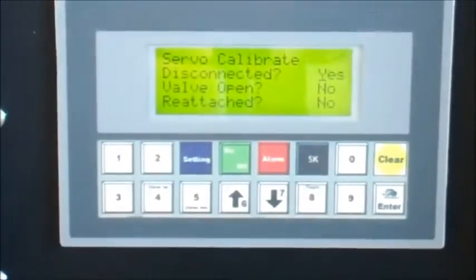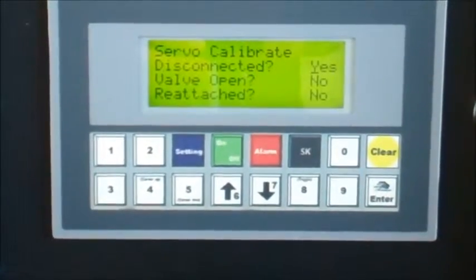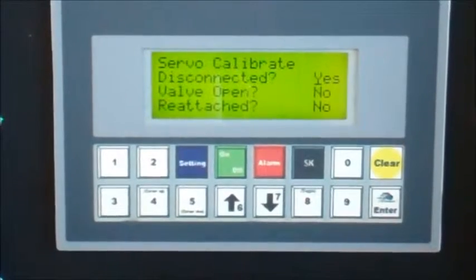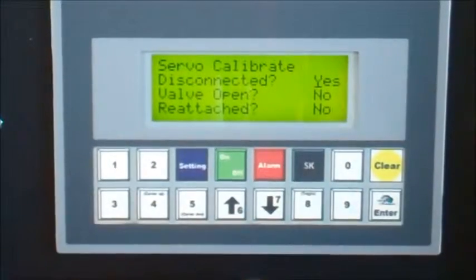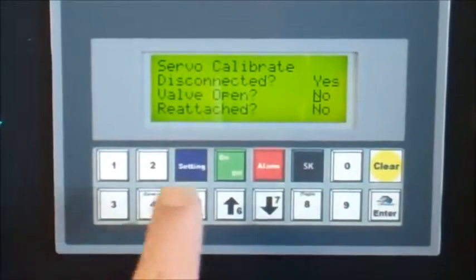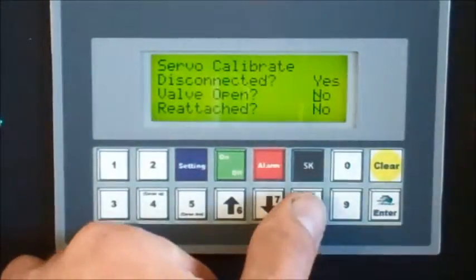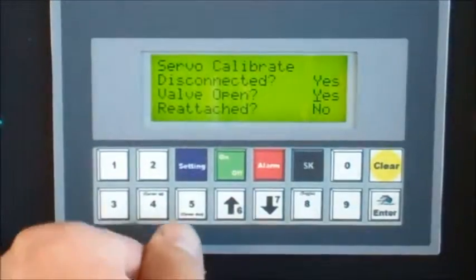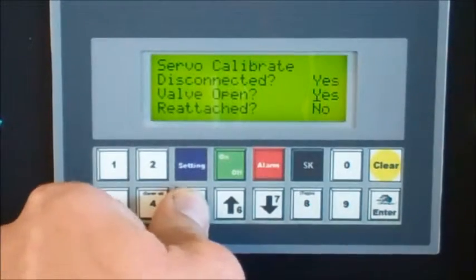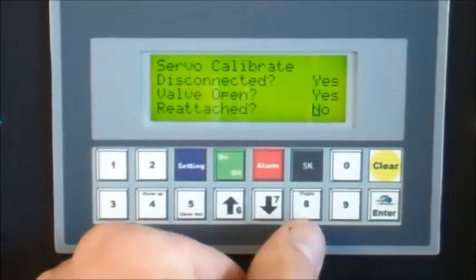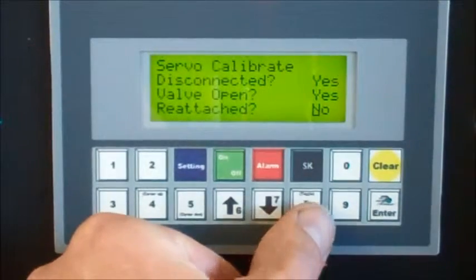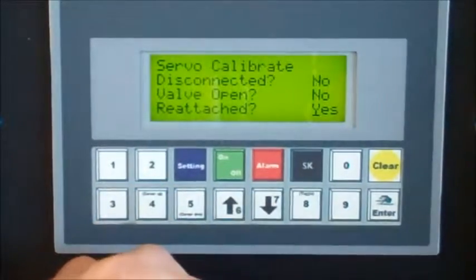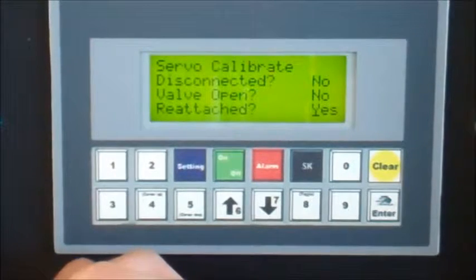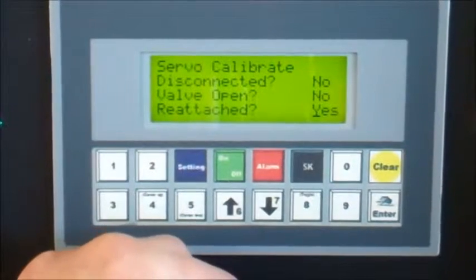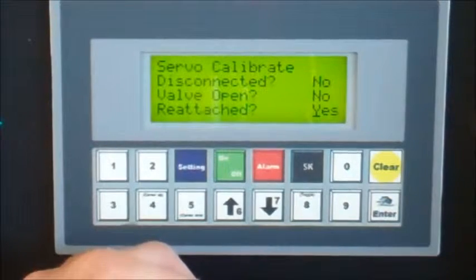Okay. Back to the local display. We will press 5 to move the cursor down to the valve open position. Toggle that to yes. We will use number 5 button to cursor down to the reattached. Toggle that to yes. The servo is now turning again and closing the valve.